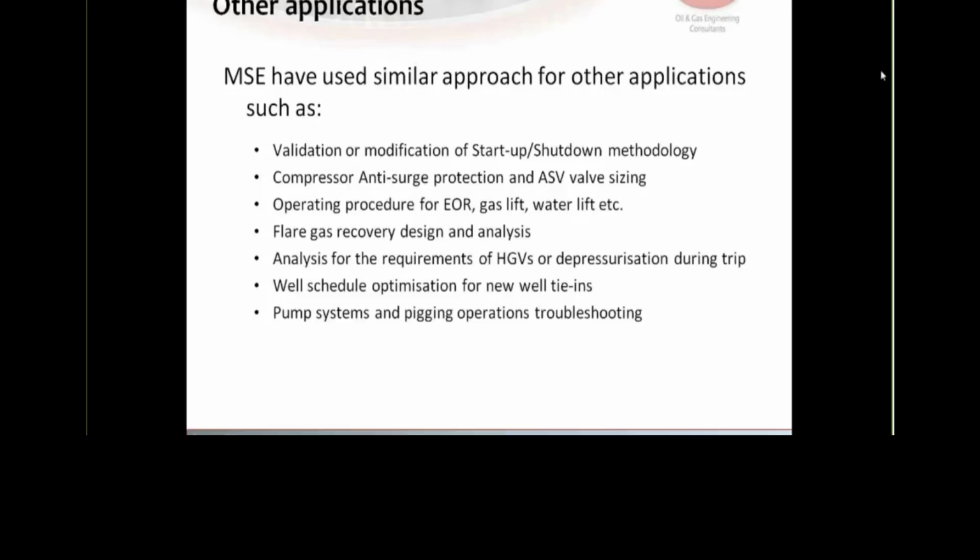Just to add on to one other thing that Kadir has said, that I do agree with you. Data sheets are easily available, but acquiring site-specific data is sometimes a bit problematic. What we have done in the past, we have gone through all the P&IDs and PFDs and specified the signal data that we require and sent it to the offshore engineer.